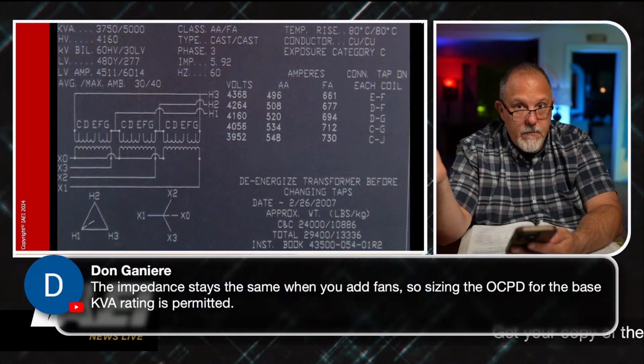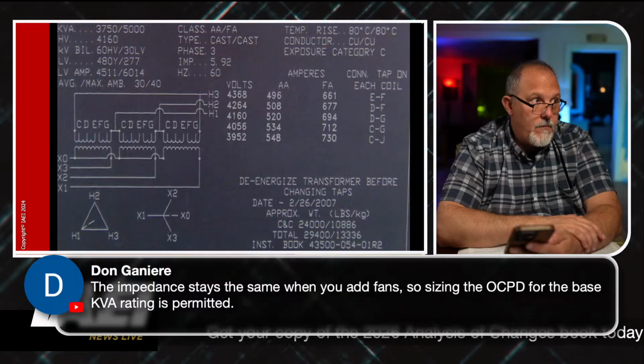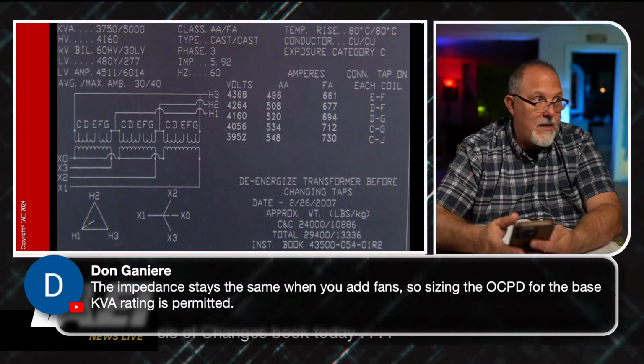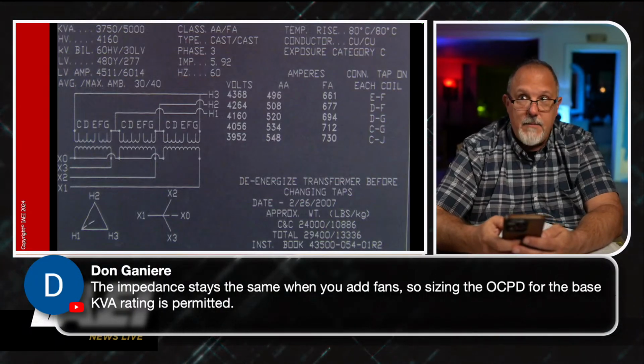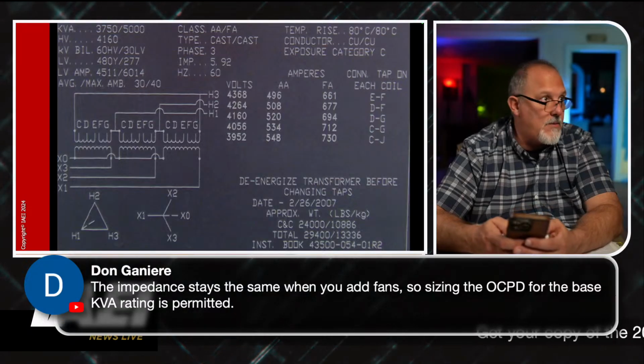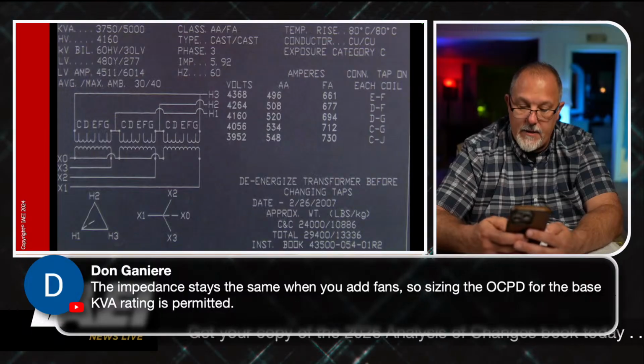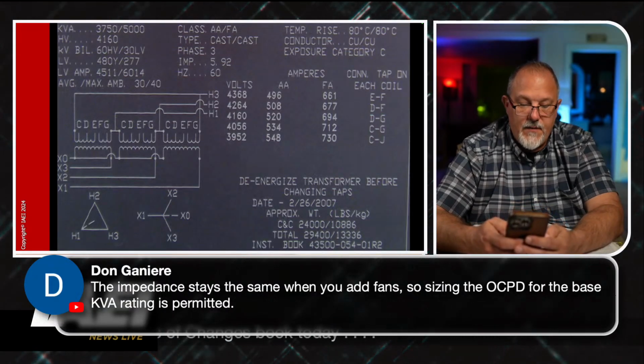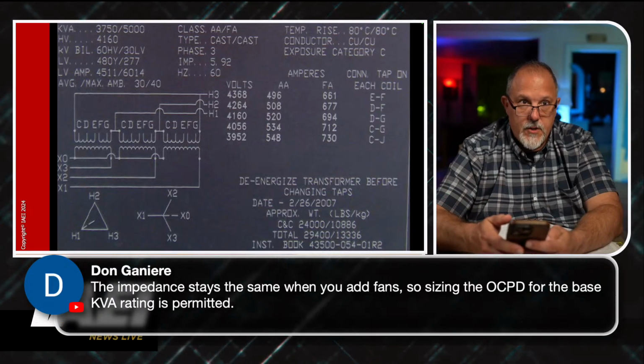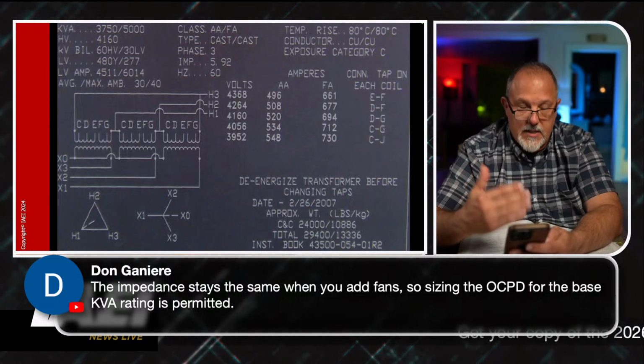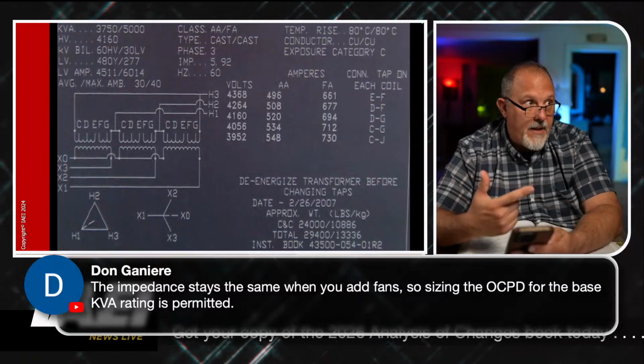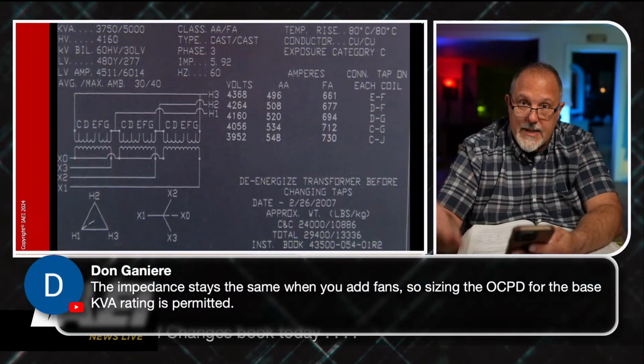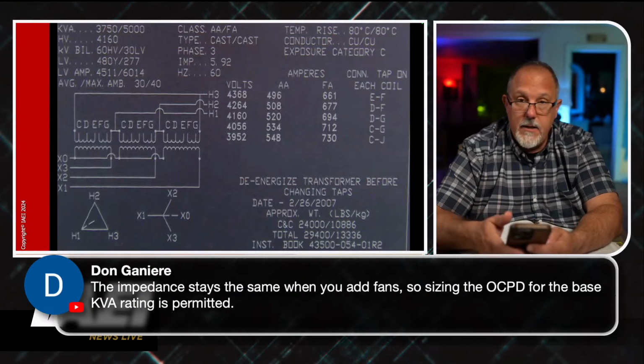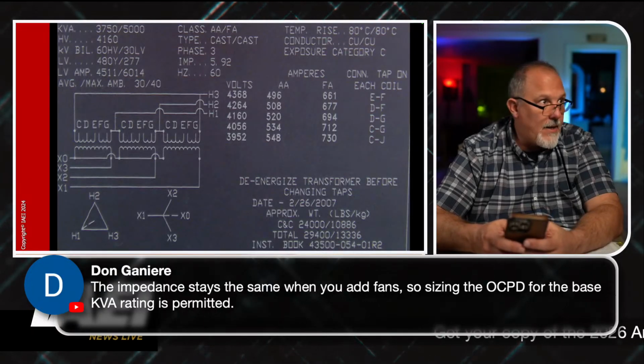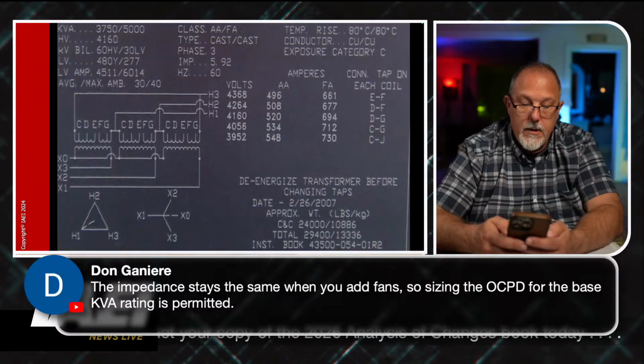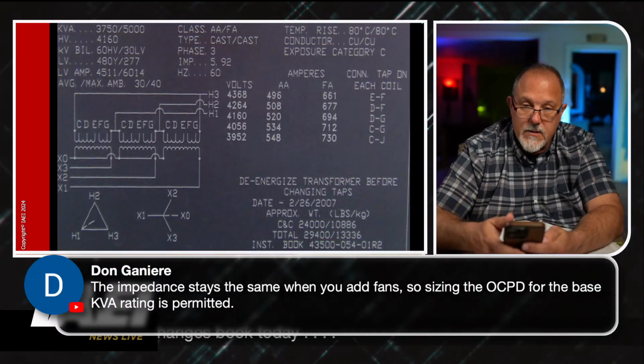Now on the secondary, here's the question. On the secondary, I'm permitted up to 125% of the full load amps on the secondary. If I say I'm going to do 125% times the full load amps at 3750, which is 4511, that's 5638. I can go to the next higher. So my equipment on the secondary wouldn't be able to exceed that. But if I'm at 5,000 kVA, I can put more load on it. So my secondary overcurrent protective device could theoretically be 1.25 times the 5,000 kVA secondary full load amps, which is 6014, and now I can go up to 7,500 or the next larger.